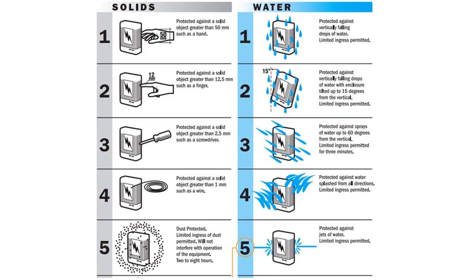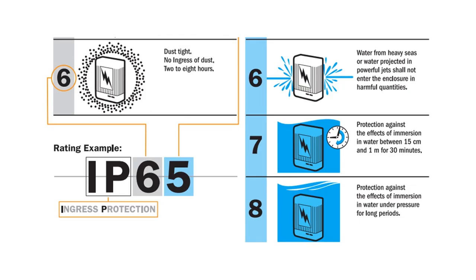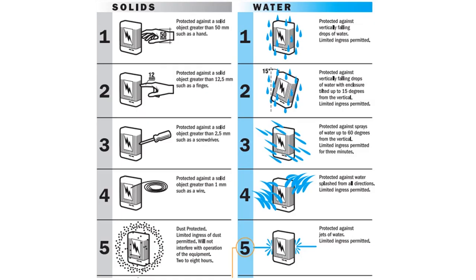In pictorial form, you can see that the first numeral indicates protection against solid foreign bodies and the second numeral indicates protection against water penetration. The commonly used IP rating for a transmitter is IP65, which indicates it is dust tight — no ingress of dust for two to eight hours under test. The second numeral five means protected against jets of water with limited ingress permitted, without having any effect on the operation of the equipment.